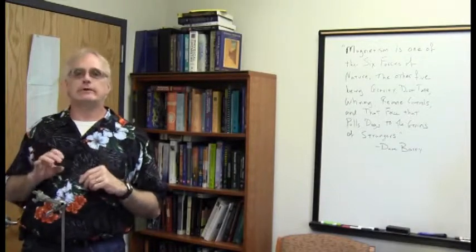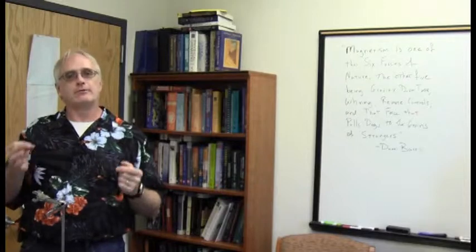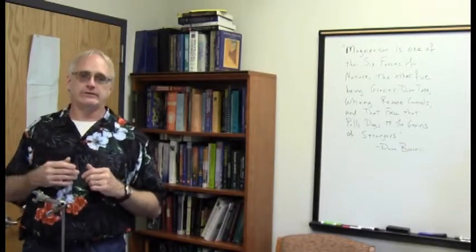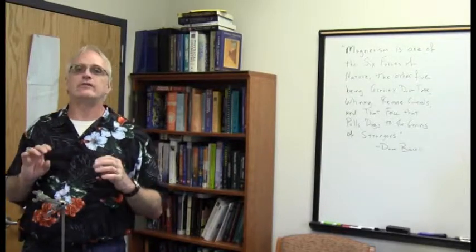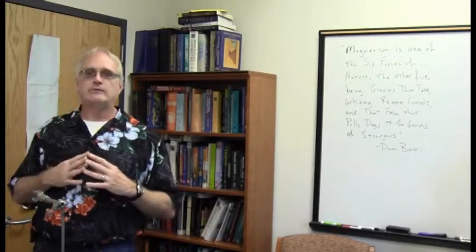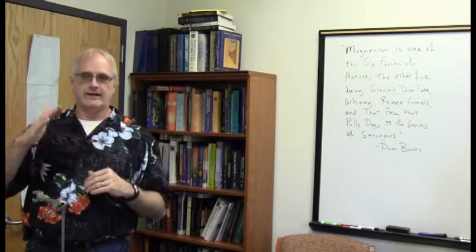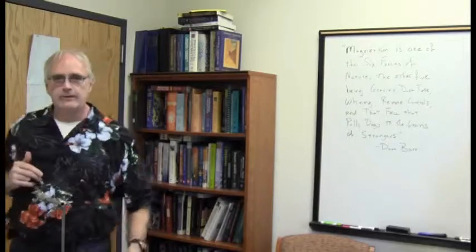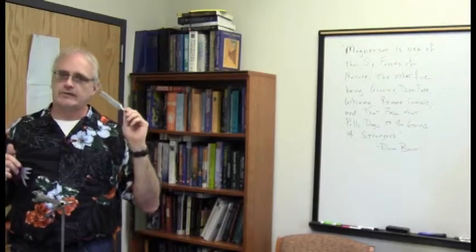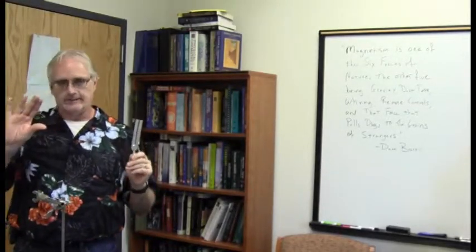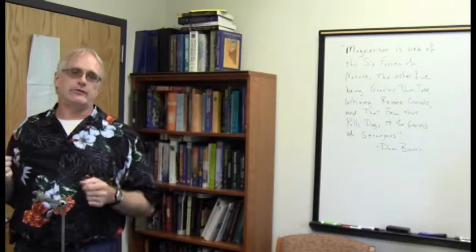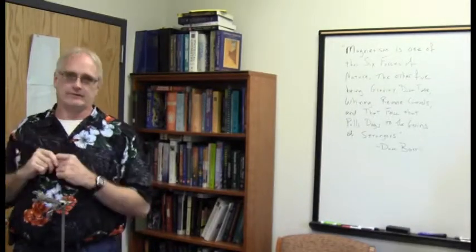So finally, I want to show you a couple of details of how we process the NMR spectra. Because what the instrument measures is not really what you see as an NMR spectrum. What it's measuring is a collection of oscillating frequencies. Now, much like the tuning fork here, when I sound the tuning fork, I hear the sound, but over time the sound diminishes as the tuning fork finally goes silent. It's essentially, I induced it to make a sound, but that sound is decaying over time.